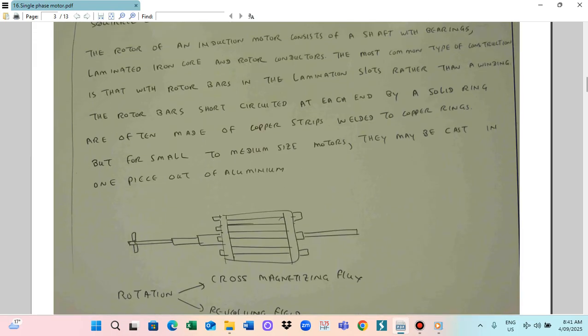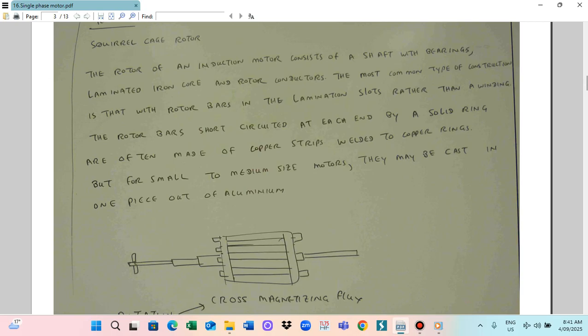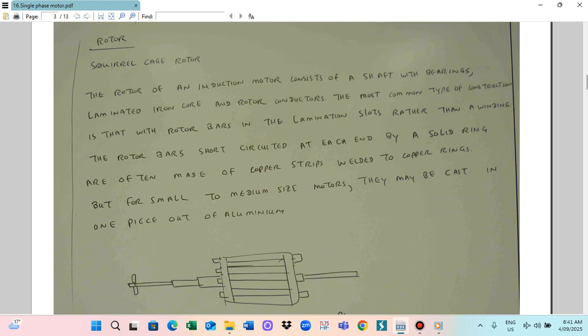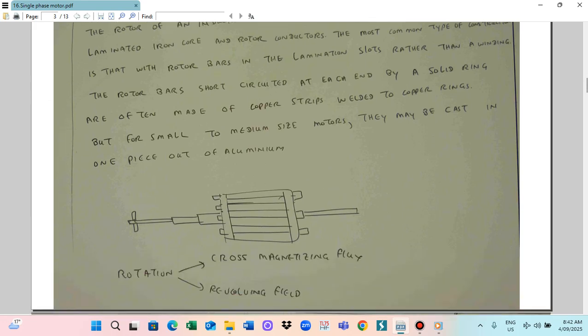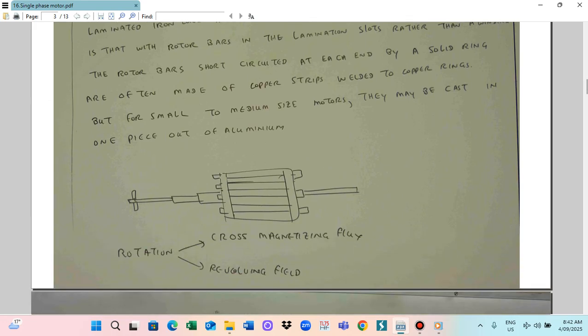the rotor circuit. So the rotor of the three-phase induction motor consists of the shaft and the bearing, laminated iron cores, and the rotor cage. The most common construction is best: the rotor bar in the laminated slot rather than the winding. The rotor bar is short circuited at each end by a solid ring, often made of copper. But for small and medium size motors, they are cast in one piece of aluminum. So this is what you see when you look at the induction motor.